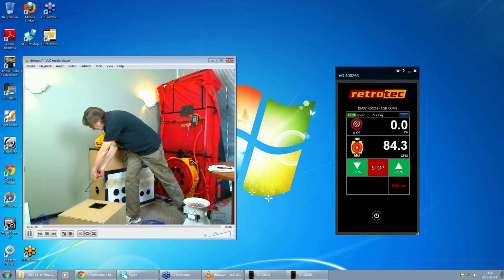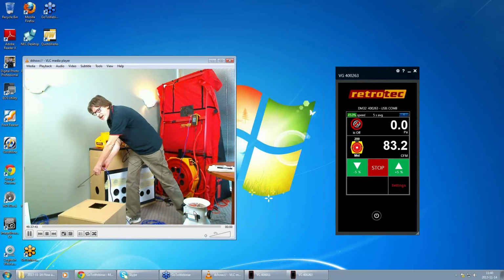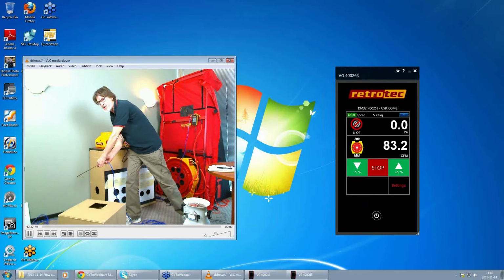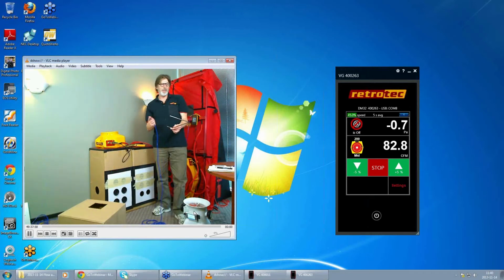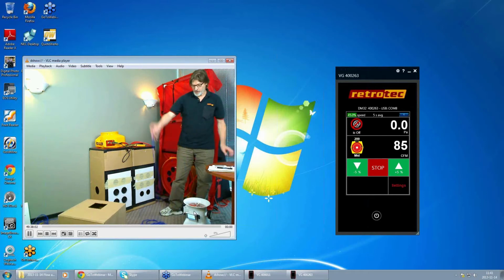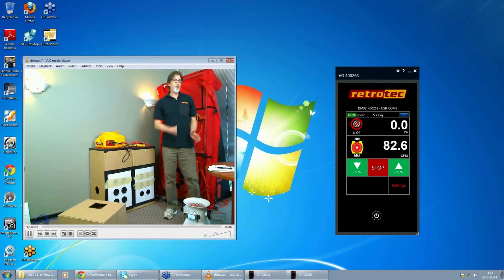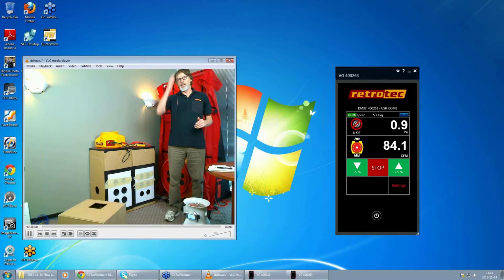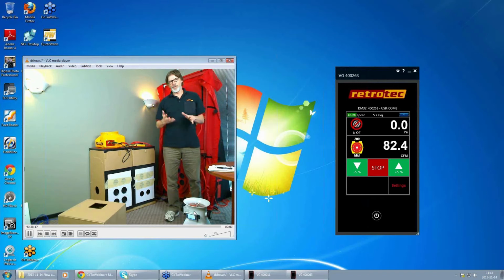So what I need to do to measure flow with this is measure the velocity times the area, and it's pretty complicated. Very few people do it. You can do it in ducts and so on. So it's a pretty fundamental tool, but it's one that requires a fair amount of skill. So it's measuring velocity. So flow is equal to velocity times the area. So that's the reason why we have these flow devices, so we don't have to bother with that. Taking a good pitot flow, using a pitot tube on a duct of this size, you might spend half an hour doing that. So if you have a flow device that we can use, like we're talking about here, we can do that much faster.